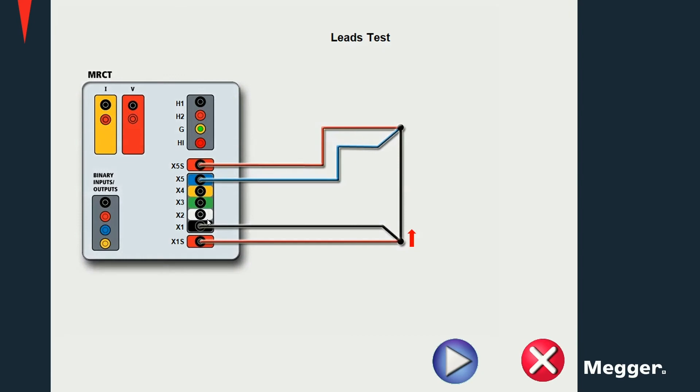A procedure that is sometimes necessary is the leads test or zeroing the leads. For this, short the secondary terminals, a DC current is injected into them, and the resulting voltage drop is measured, which allows us to calculate the resistance of the leads.